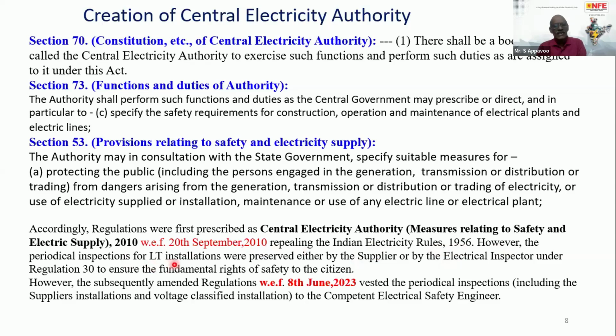The periodical inspection for LT installations was preserved either by the supplier or by the Electrical Inspector under Regulation 30. This is to ensure the fundamental right of the citizen. Every installation should be inspected by the authority, by the enforcers. That's the intent. Because the strength of the electrical inspectorate organization in our country is very weak, very meager, they have entrusted the crores and crores of consumers to the purview of the supplier. This is the intent. This was existing since 1956 itself.